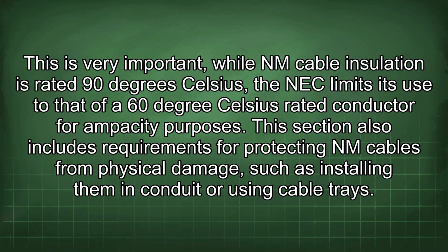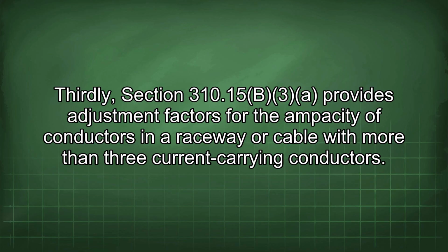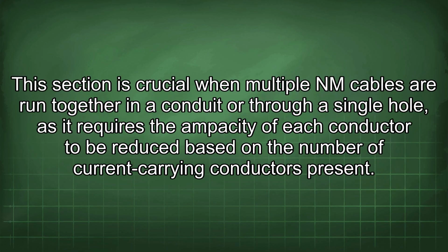This section also includes requirements for protecting NM cables from physical damage, such as installing them in conduit or using cable trays. Thirdly, Section 310.15(b)(3) provides adjustment factors for the ampacity of conductors in a raceway or cable with more than 3 current carrying conductors. This section is crucial when multiple NM cables are run together in a conduit or through a single hole, as it requires the ampacity of each conductor to be reduced based on the number of current carrying conductors present.